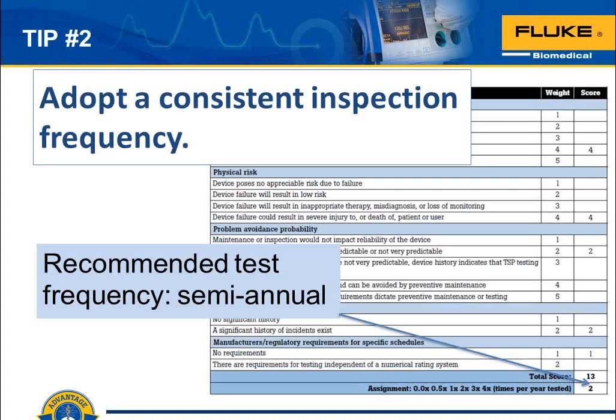There are risk criteria that are provided. They're divided into 5 categories: clinical function, physical risk, problem avoidance probability, incident history, and regulatory or manufacturer requirements. The device that we're trying to score and come up with a frequency of inspection is given a score for each of these categories. The scores for each category then are added up to come to a total score, and for that total score, we have a scorecard for determining how often it should be inspected.